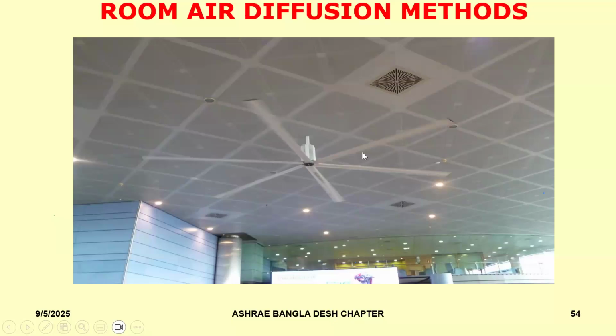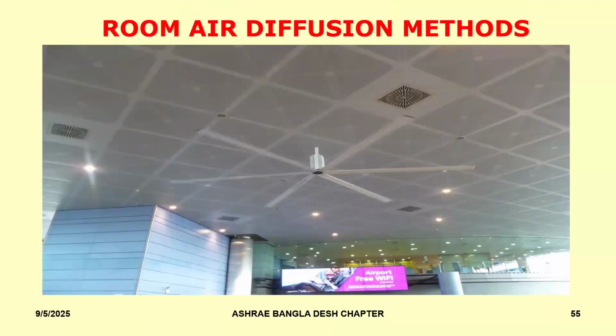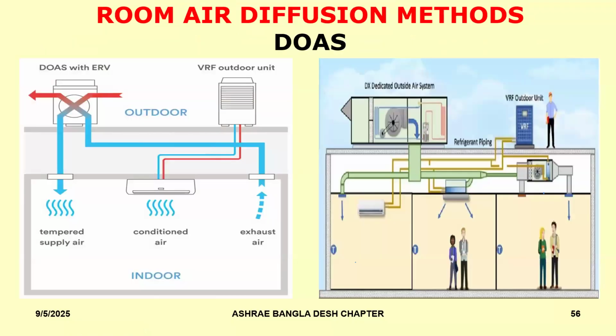fans at those times. Also, at certain times during the cooling season, if you find that the occupancy has gone up substantially, what you can then do is to use these fans and increase the air velocity over the people, and therefore be able to keep them comfortable. So these are also methods by which you can intentionally increase the airspeed to keep people comfortable.